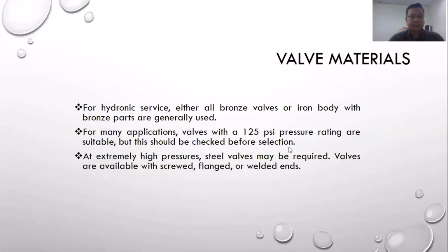Valve material. Okay, valve material for hydronic service: either all bronze valves, or iron body with bronze parts, are generally used. For many applications, valves with a 125 pounds per square inch rating are suitable but should be checked before selection. At extremely high pressure, steel valves may be required. Valves are available with screw, flange or welded ends.